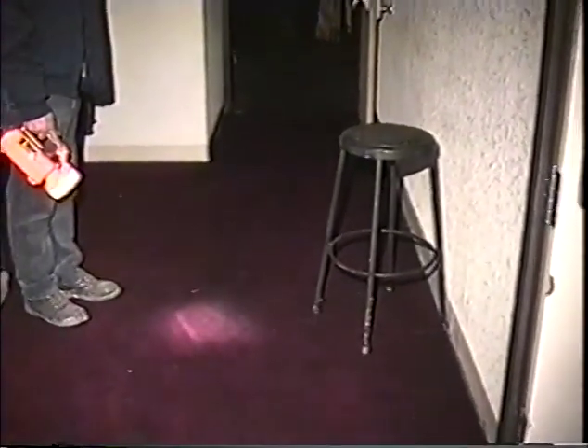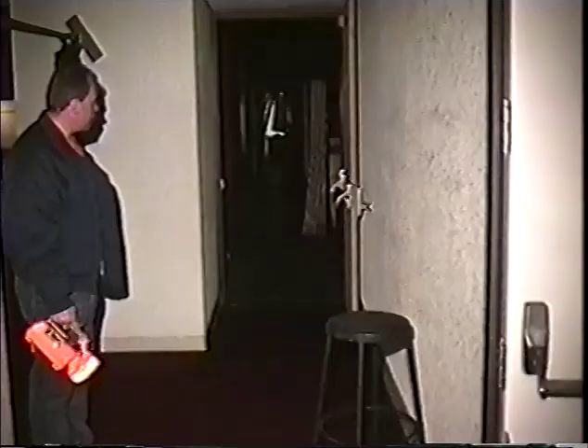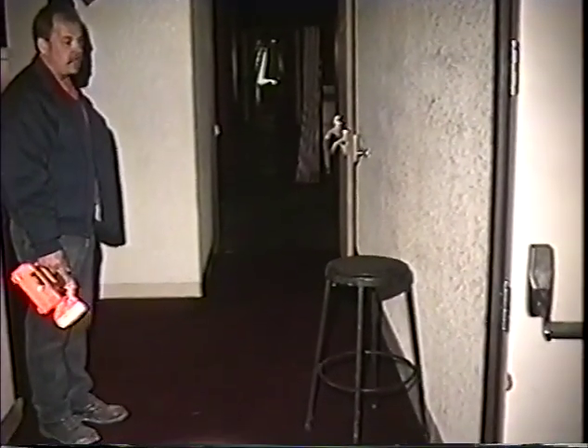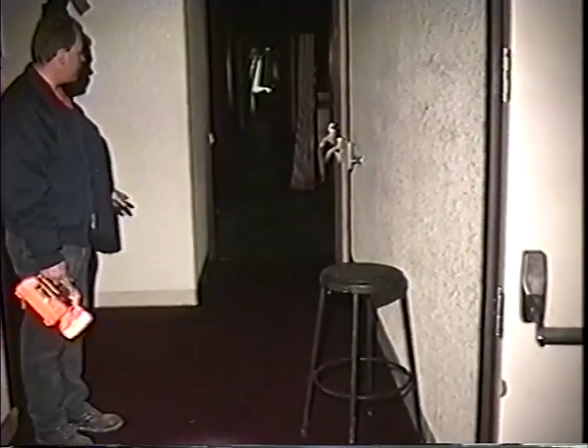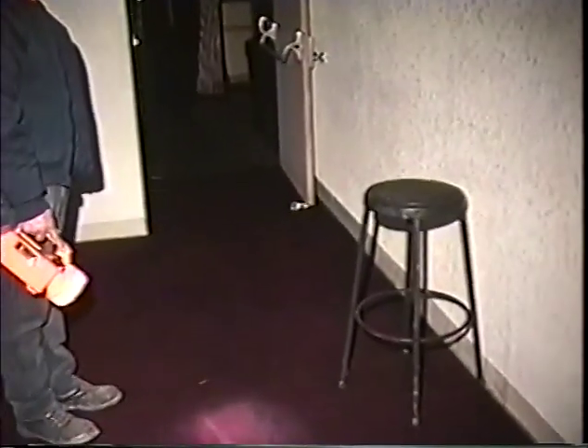We're showing supporting evidence of what we feel the arsonist attempted to do to allow rapid spread of the fire to other areas of the school by taking doors which are rated doors on self-closing devices, which are required to be closed at all times other than when people are passing through the doorway, where these doors have been propped open, chocked open, or blocked open by various devices to allow spread of hot gas and flame to other areas of the building.